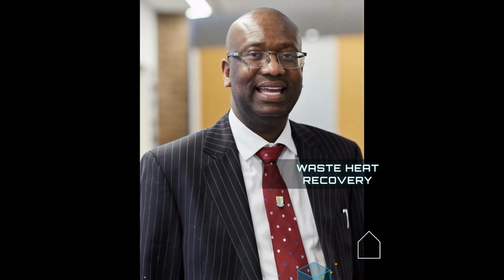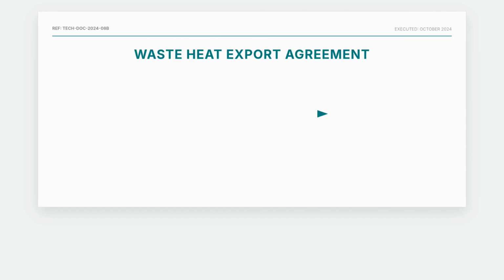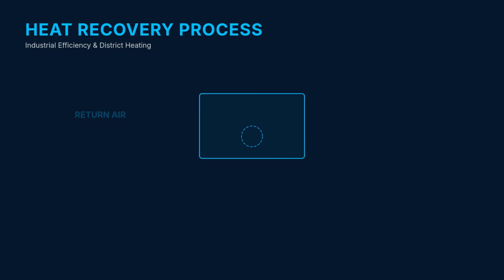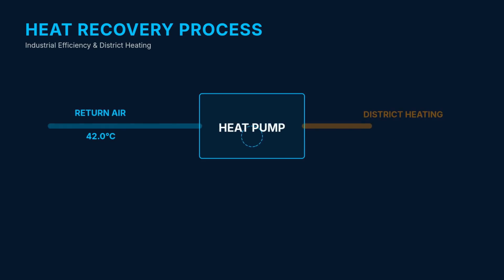85 megawatts of critical IT load generates exactly 85 megawatts of heat energy. At Iron Gate, that heat was simply lost to the atmosphere. At FULCRUM, we treat it as a commercial resource. We have a legally contracted waste heat export agreement. We capture hot return air from the hall and transfer that energy to the local district heating authority for use in the community. Using air-to-water heat exchangers, we capture return air at 42 degrees.